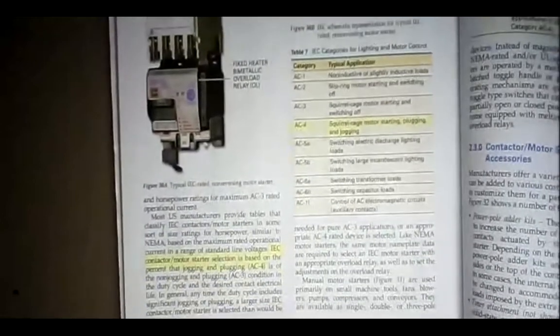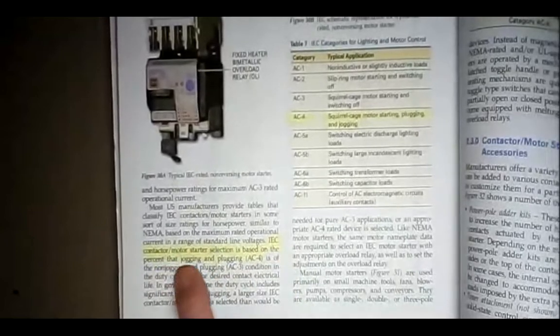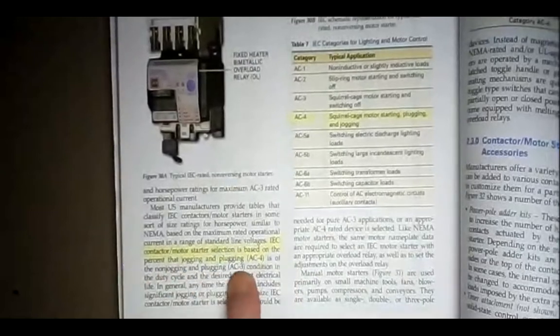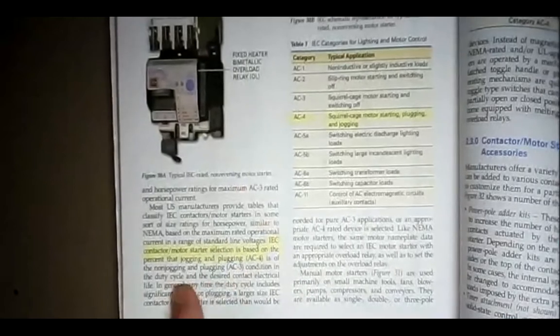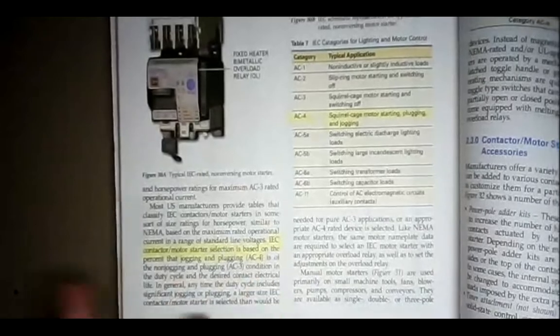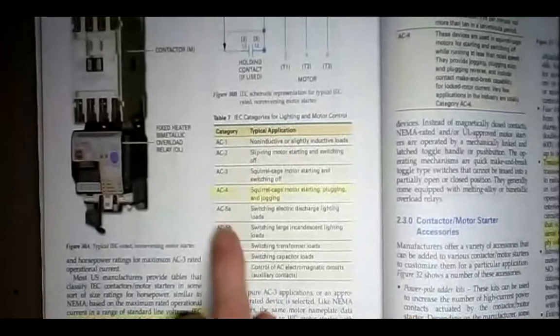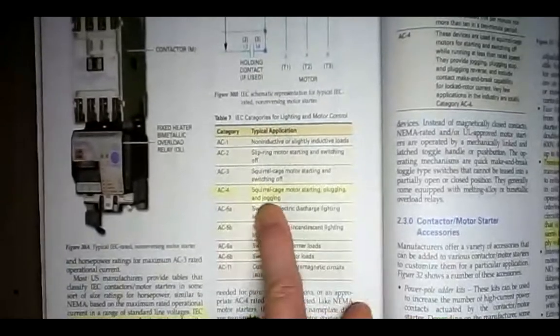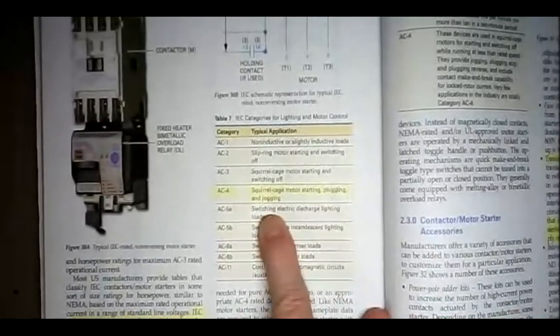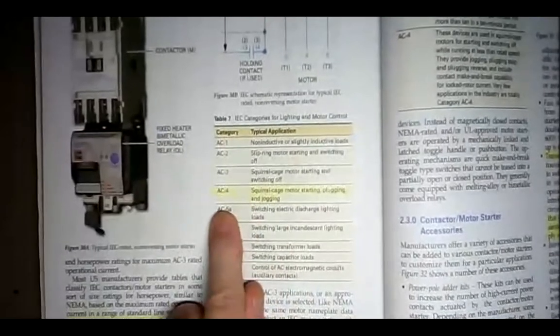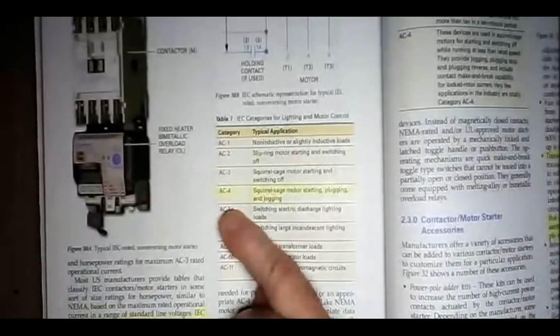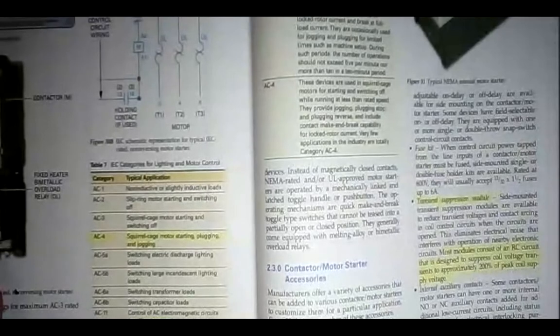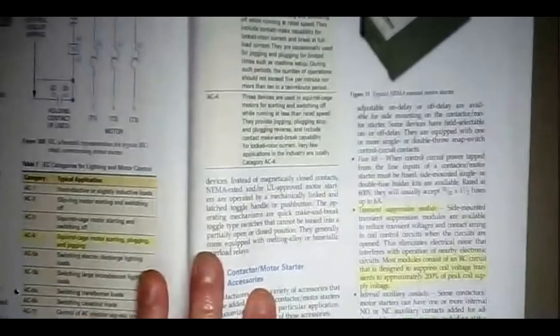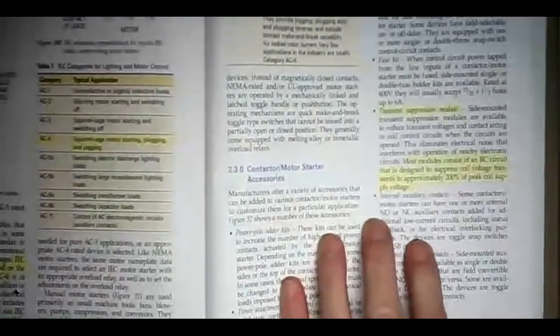On page 28, very bottom of the left-hand side, it says IEC contactor motor starter selection is based on the percent that jogging and plugging is of the non-jogging and plugging condition. So here's table 7 on the right-hand side of page 28, and I have an AC4. That's the category. The typical application is a squirrel cage motor starting, plugging, and jogging. You'd want an AC4 motor starter. That's that IEC designation. Okay. And they do have some crossover charts that tell you if it's this size NEMA, it would be this size IEC.